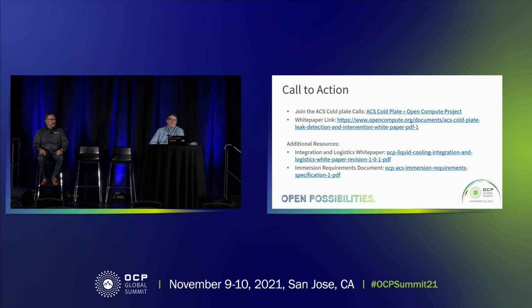Historically, where we've been with connectors is it's been very vendor specific. UQD and the work within OCP around a standardized connector, and the other blind mate connector within OCP, are good examples of - it may not be the best solution, but it's a starting point. It solved the problem that we had at the immediate. As an infrastructure vendor, we're constantly working with a lot of the connector vendors - we'll use a connector until it creates a problem or until a customer tells us there is a problem, then we have to go back and make tweaks.